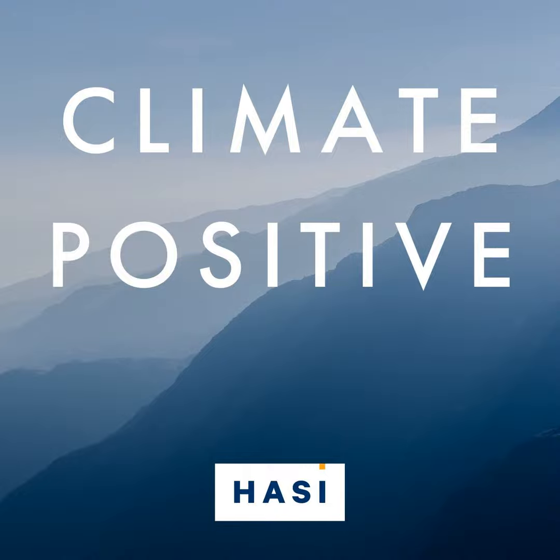Now, it's worth noting when Scope 2 accounting was written, A, the data didn't exist to do that math, and B, at the time, it was probably closer to 450 in California. The reason California has dropped from 450 isn't about a gas plant, right? The reason it's 150 in California is because in large portions of the day, the California grid is totally clean. You can add more demand at that location, and it will uncurtail a solar project that's shutting down because there's more solar than the grid can absorb. So in the middle of the day, the carbon value of power might be 0 tons of carbon per megawatt hour, whereas it's close to half a ton at night when the sun goes down and the gas plants ramp back up to fill it in.